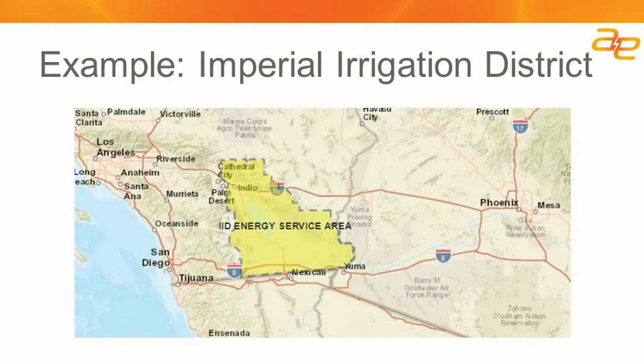So the problem is that the transmission lines leaving the IID area don't have enough capacity to take all of the energy when it's both very sunny and very windy. And therefore, some of those sites need to be curtailed to outputs lower than their design capacity or shut off altogether in order to limit the energy flow to the maximum amount the transmission system can handle.